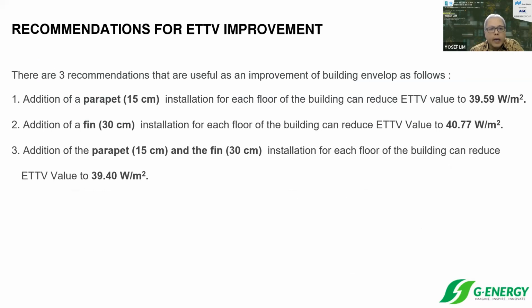The first recommendation was adding a 15 centimeter parapet installation for each floor, which improved the ETTV to 39.59 watts per square meter. The second recommendation was adding a 30 centimeter fin installation for each floor, improving the ETTV to 40.77 watts per square meter.